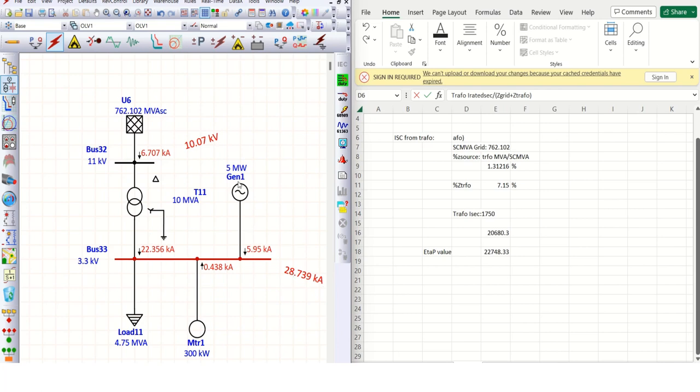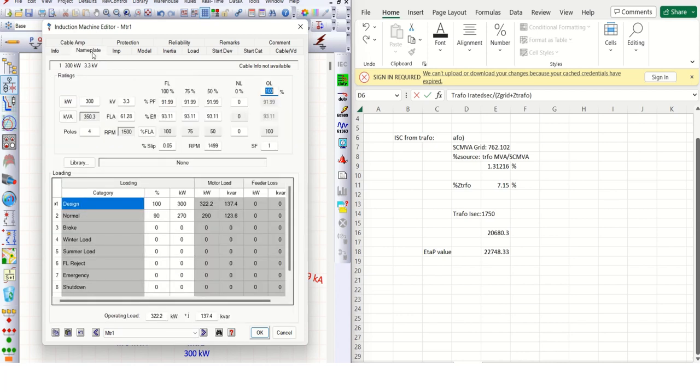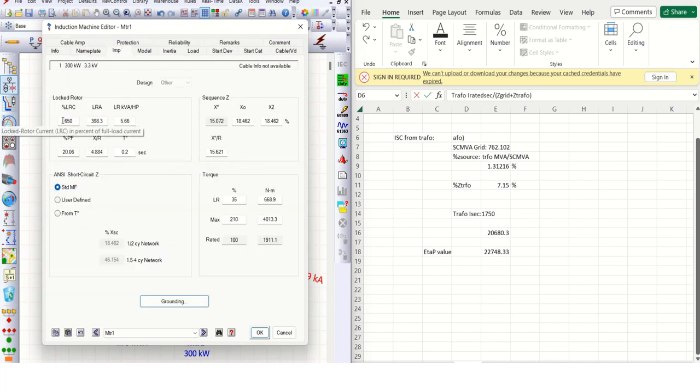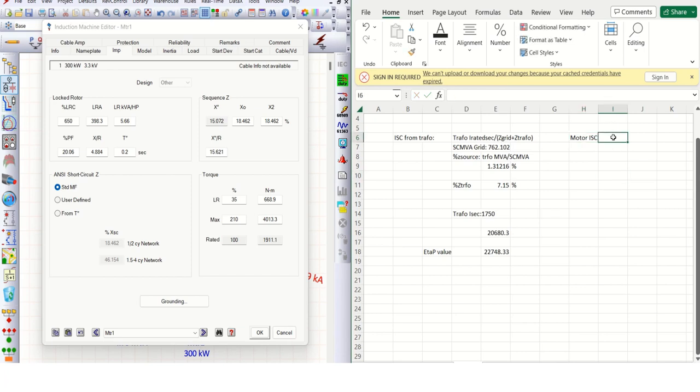Then coming to the motor, what is the motor value? 300 kilowatt rating. So go to nameplate detail, a rated current of 61.28. When you move to impedance, this is what decides your short circuit current, 650%. That means the motor short circuit current is percentage LRC divided by 100 multiplied by I rated. What is percentage LRC?